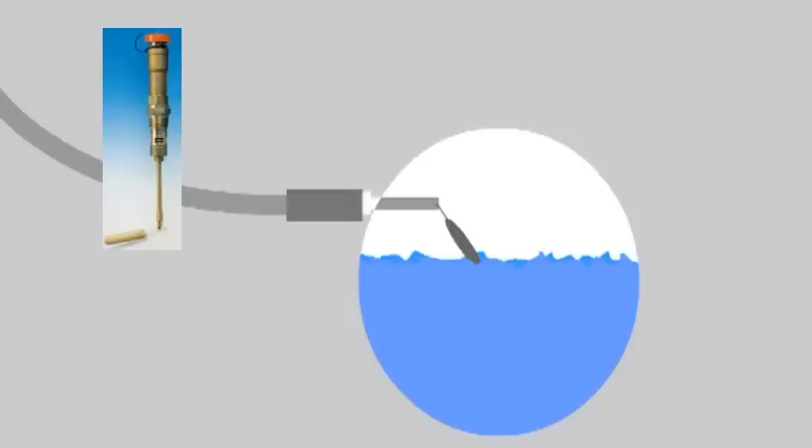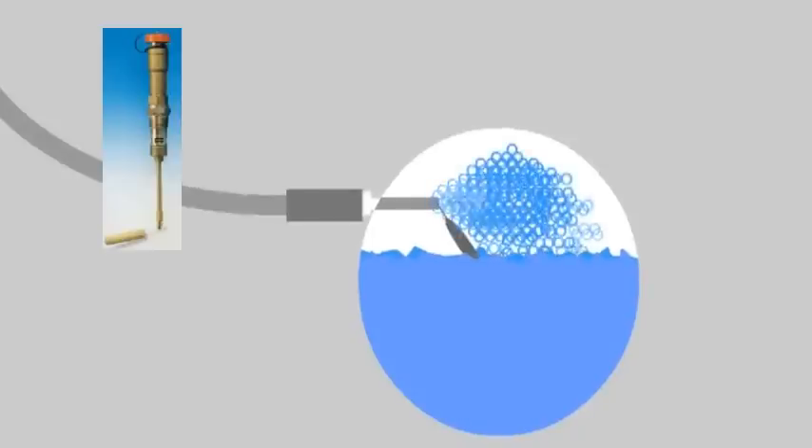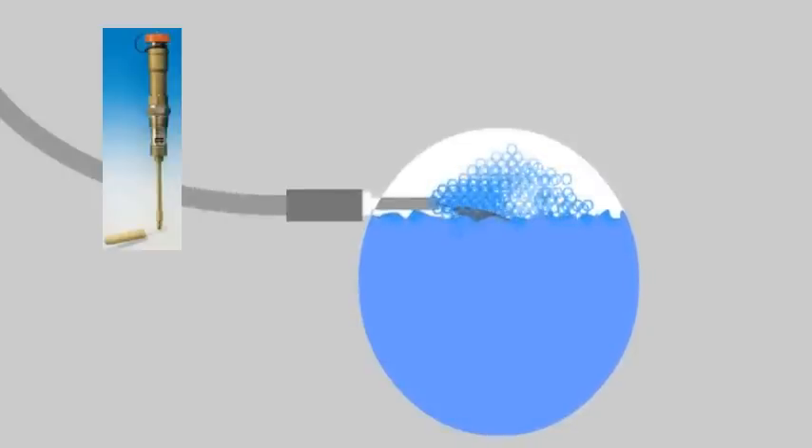Another important safety feature installed on all Blossman propane systems is the automatic stop fill device used during the filling process. Notice that when the liquid level of propane inside the tank reaches 80% of capacity, the automatic stop fill device prevents any additional fuel from entering the tank. This safety feature ensures that the propane container will not be overfilled. With routine inspection and proper usage, your Blossman propane system is many, many times safer than a conventional gasoline installation.